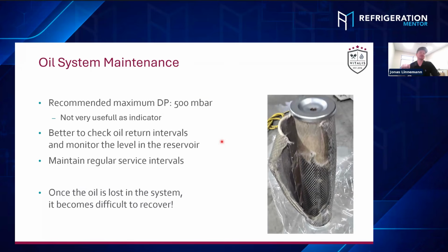So typically, whenever I'm at a startup, I always try to listen to the oil return solenoid valve, because once in a while, every few minutes, you just hear a little click, and then you know, okay, the oil separator is doing its job, and you do not even have to look after the oil separator, I would say. So if you come on site and want to figure out if the oil separator is doing its job or not, as long as 1, 2, 3 compressors are running, the oil separator should return a chunk of oil every 5 to 10 minutes.